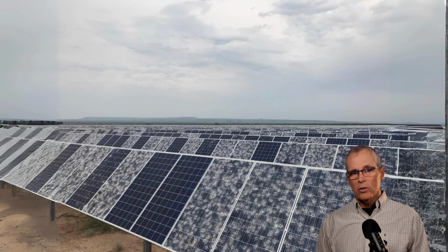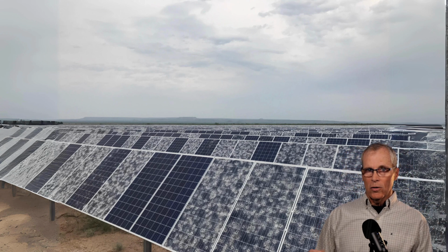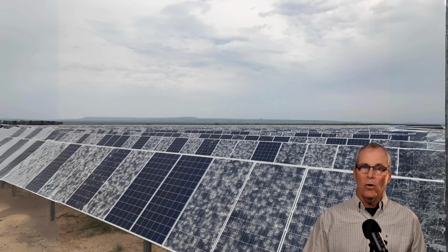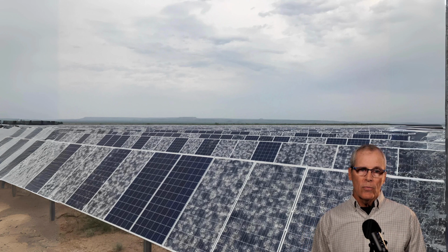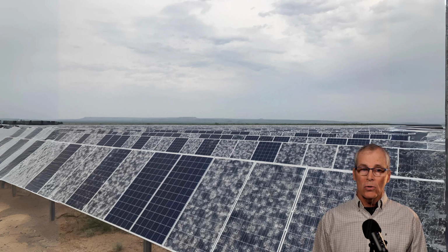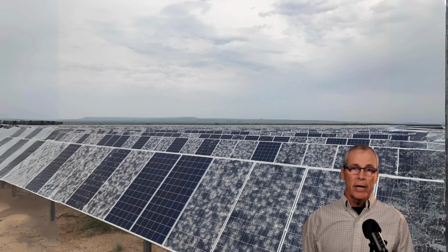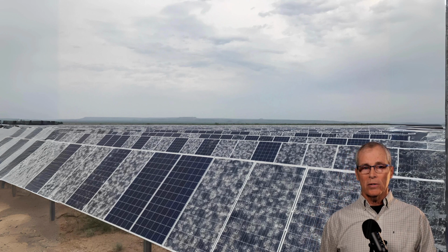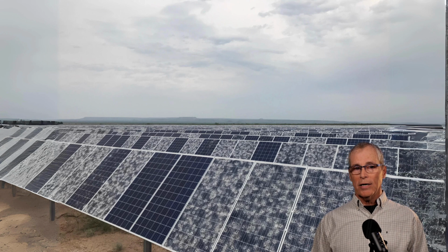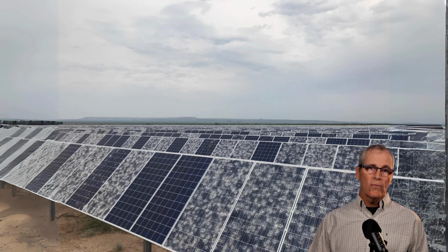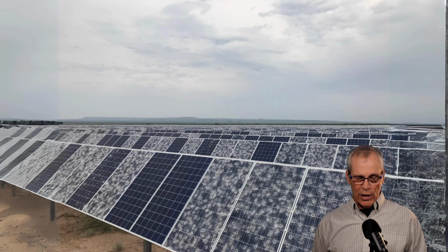But if you notice, not every single panel is destroyed. And this can cause problems for folks who aren't used to solar hail interaction. What can happen is the adjuster will look at those panels that don't appear to be damaged and make a blanket statement that they're not going to pay for them because they're not cracked. Well, you can't see microcracks. So whether they're covered or not, it doesn't mean that panel is a good panel going forward if it's got microcracks. We'll get into microcracking later.